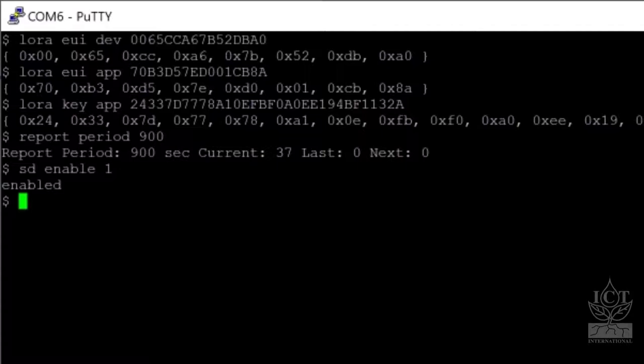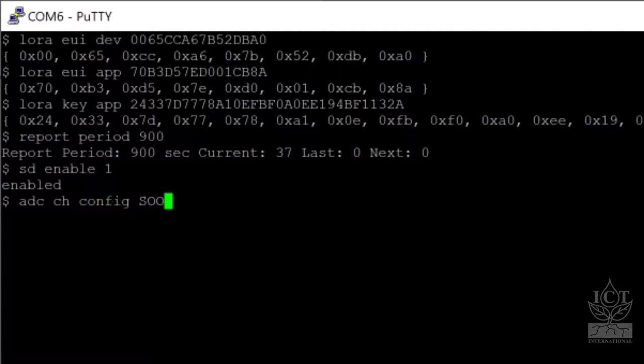To enable the analog channels on the MFR node, use the command ADC CH CONFIG followed by the channel definitions. Capital S indicates a single ended channel, capital D indicates a differential channel, and capital O sets the channel to OFF.